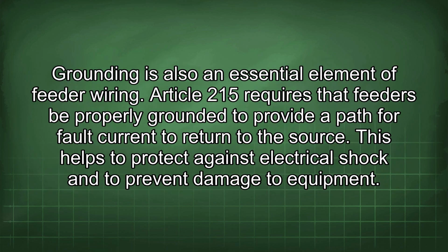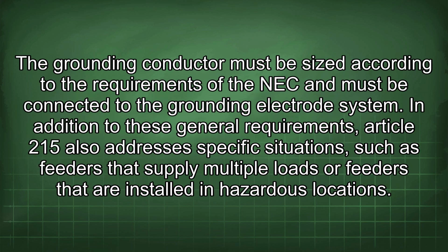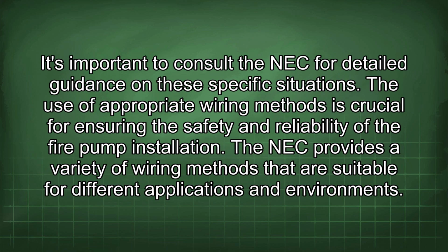Grounding is also an essential element of feeder wiring. Article 215 requires that feeders be properly grounded to provide a path for fault current to return to the source. This helps to protect against electrical shock and to prevent damage to equipment. The grounding conductor must be sized according to the requirements of the NEC and must be connected to the grounding electrode system. In addition to these general requirements, Article 215 also addresses specific situations, such as feeders that supply multiple loads or feeders that are installed in hazardous locations. It's important to consult the NEC for detailed guidance on these specific situations.